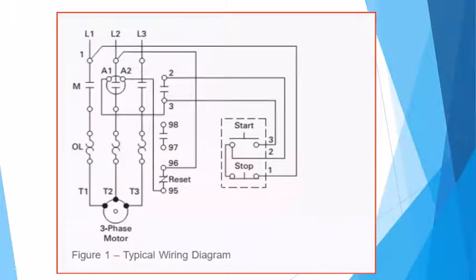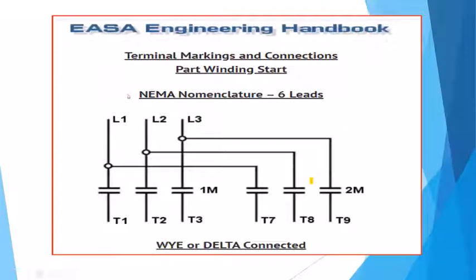So from that point, they went on and they created part winding. So they would switch in just half of the winding here with 1, 2, and 3. And then after it got up to speed with the time delay, they would bring in the other half of the winding. This is still done quite a bit with contactors, but it's a way of also starting that motor.